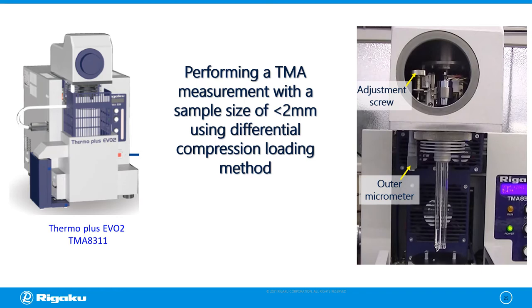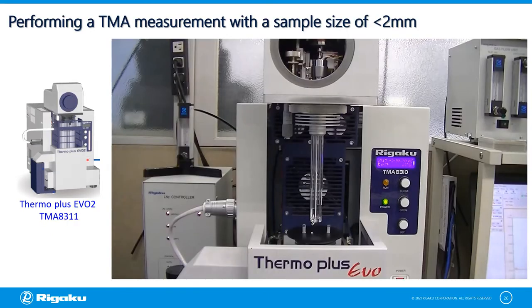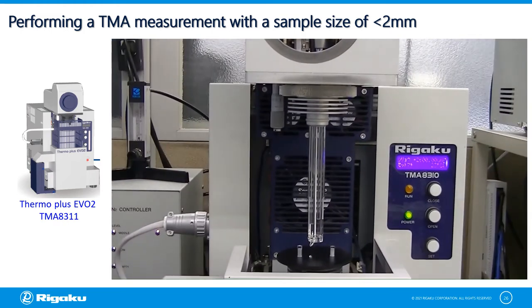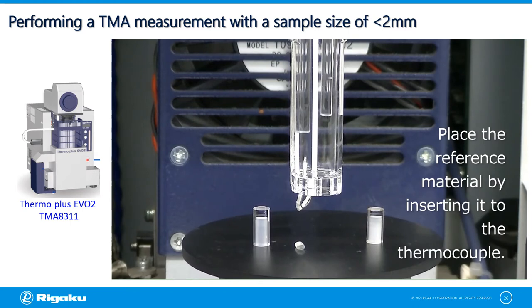In the next video, we will show how to perform a measurement with a sample length of less than 2 mm using the compression loading method. By using a sample stage of 10 mm in length, you can measure samples with less than 2 mm in length. It is ideal that the total sample length including the sample stage is nearly the same as that of the reference material. In this case, we use the 11 mm reference material.